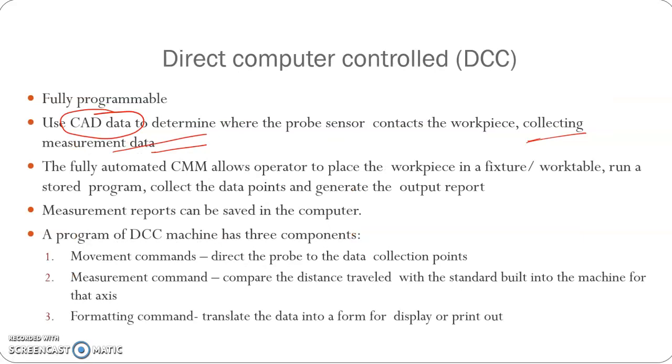In DCC, the sequence of operations may be like this: the operator places the workpiece on a fixture, then runs a stored program. Then the CMM automatically collects the data points and generates the output reports. The program of DCC machine has three components: the movement commands, measurement commands, and formatting commands.